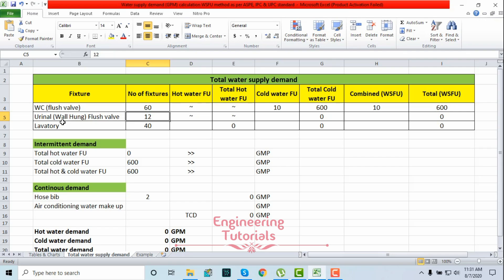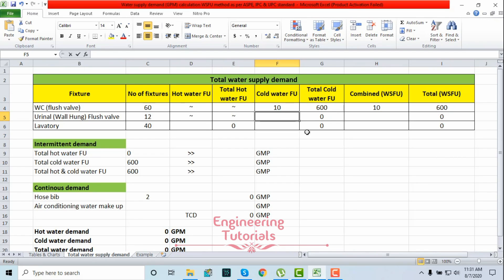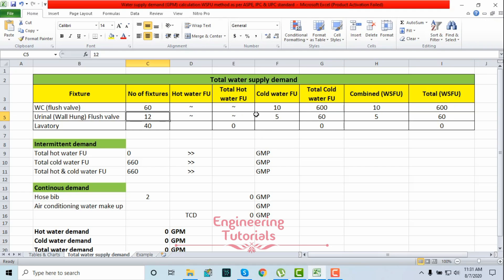For urinals we have 12, wall hung flush valve type. Going back to the chart: stall or wall urinals with flush valve — cold water required is 5 fixture units and total is also 5. So we write cold = 5 and total = 5 for each urinal. Multiply the number of fixtures by the fixture unit value to get the total: 5 × 12 = 60 total water supply fixture units for cold water, and also 60 for combined.